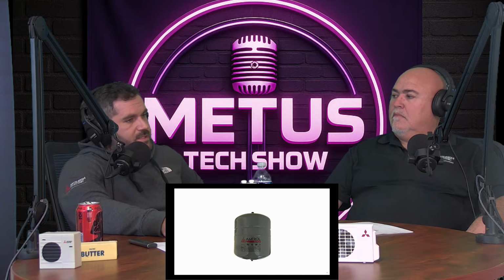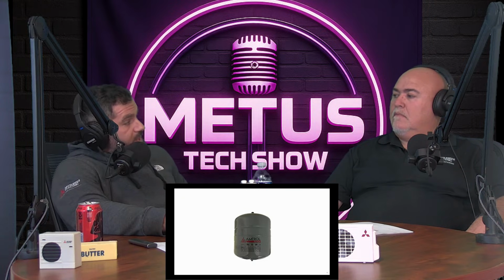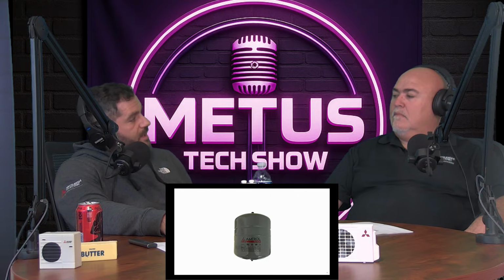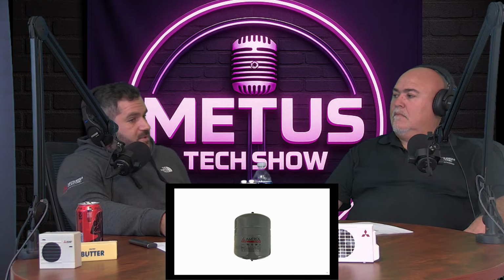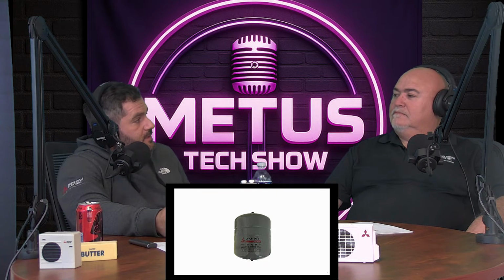So it's a good idea to keep an eye on it. It's something I used to do in preventative maintenance. When I would do hydronic systems and I would do preventative maintenance, one of the things I would do is give it a tap on the top and the bottom, make sure it was hollow on the bottom. Just because it's one of those things that's known to fail, and you may not notice it, especially in the summertime when there's not as long of run cycles.